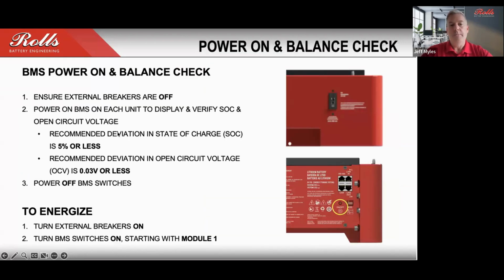On that unit, I mentioned before that there's a BMS switch that would allow you to check the state of charge of the battery and potentially complete a balance on the batteries as needed. On the rear of the unit, there's a small red power button, and if you put that on, the display on the front of each one of the units will come on. What you're looking for is to ensure that the state of charge from battery to battery is within roughly 5%, and then no more than 0.03 volts off.